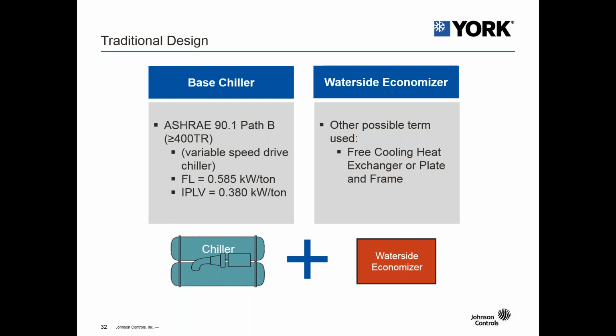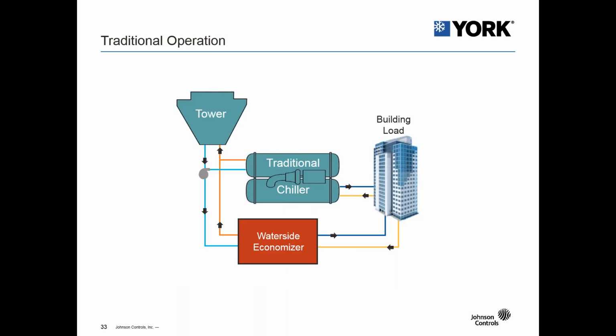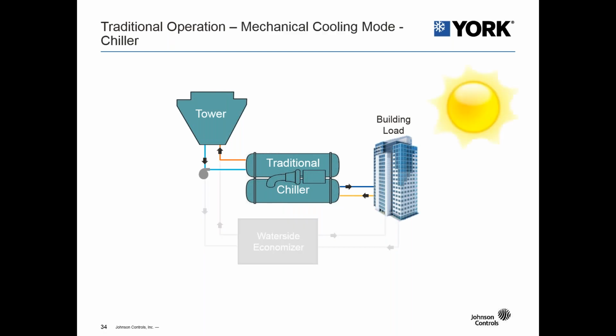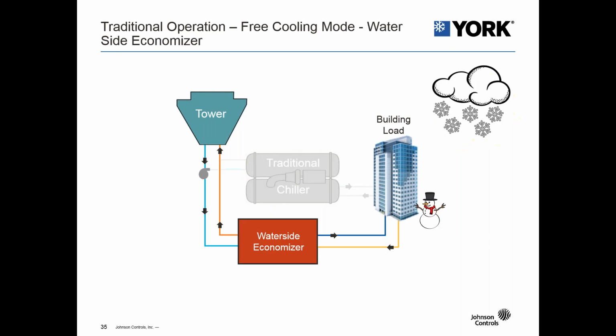And then that's also being used with a water side economizer, or commonly referred to as a free cooling heat exchanger or plate and frame heat exchanger. So here's our simple schematic. It's the towers connected to the chiller and also the water side economizer. So we're able to provide chilled water to the building load. So typically in mechanical cooling mode or in the summertime in chiller mode, the water side economizer will be off, and the chiller would be providing 100% of the mechanical cooling requirement to the building. In the wintertime, the system would enter into a free cooling mode where the water side economizer would provide all of the free cooling or the required cooling to the system.